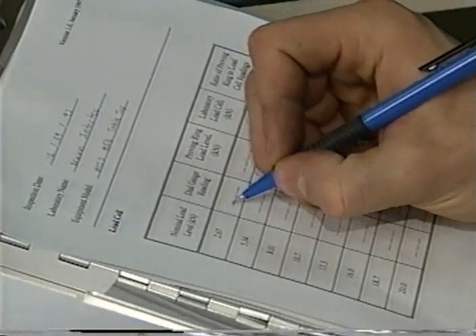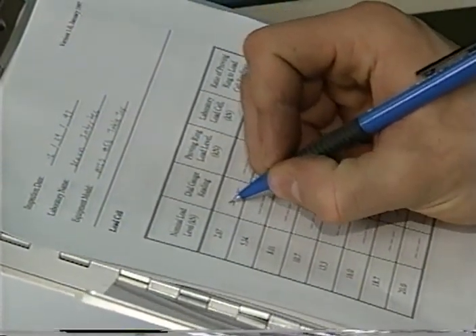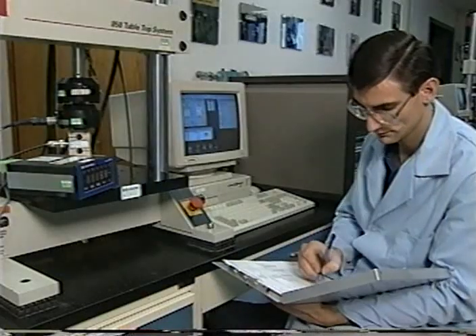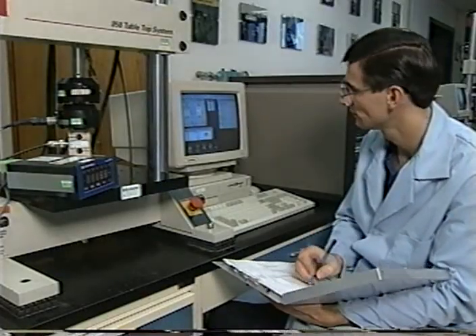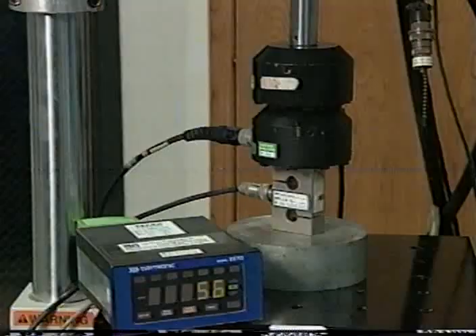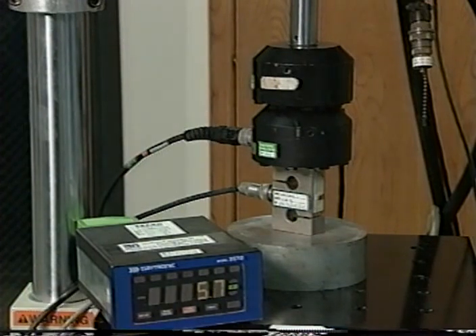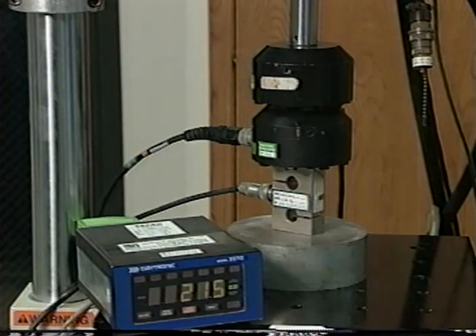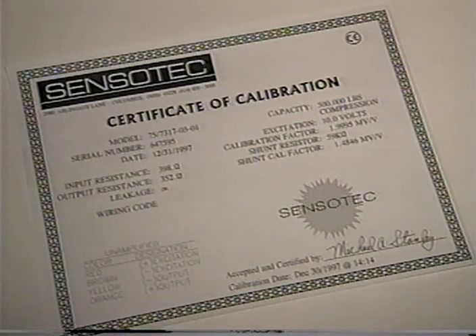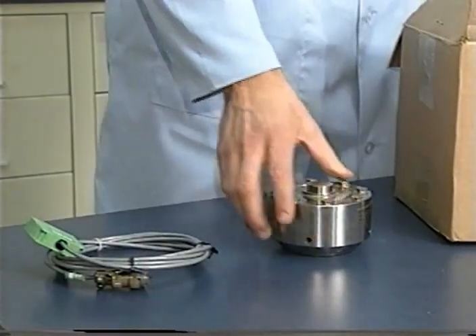The last part of the overall system test is to check your triaxial pressure chamber to be sure it can maintain a series of prescribed pressure levels for 10 minutes each. After all these tests, you need to fill in the standardized report forms included in RD 96176. You should re-verify your system at least annually and also right after any repair or relocation of the test equipment — that's especially important for load cells. They're easily damaged, and since there's only one in the test setup, it won't always be obvious when a load cell has been damaged. You should always have on hand a current calibration certificate for each load cell used in your lab.